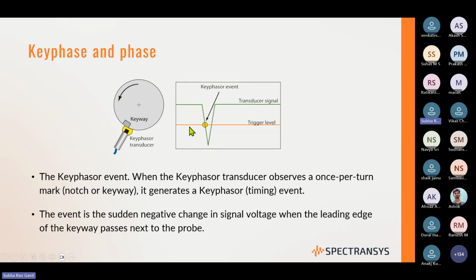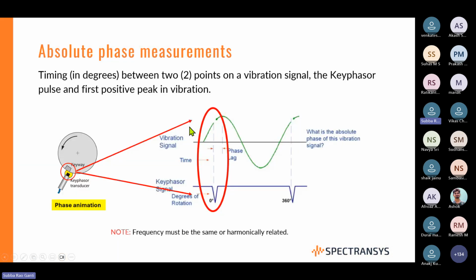This timing event is projected onto the vibration data. On top you see the green waveform, which is the vibration coming from a sensor. When the key phasor event is superimposed, the bottom is the key phasor event. The starting of the key phasor event shows up as a gap, and the ending of the key event shows up as a bright spot. So the gap and the bright spot indicate the direction in which the keyway is moving.